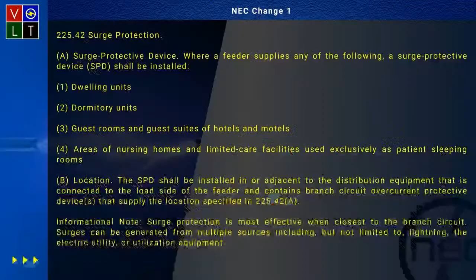All right, now this is getting into the new code changes. We'll be looking at 225.42A through E, through 230.67A. This particular one I actually saw yesterday when Mike was touching base on it, and it seemed like he was throwing the manufacturers under the bus. But what this is talking about is your surge protective devices, and it discusses where they shall be installed. You're going to see all the new areas like dwelling units, dormitory units, guest rooms and guest suites of hotels and motels, and also areas of nursing homes and limited care facilities used exclusively as patient sleeping rooms.